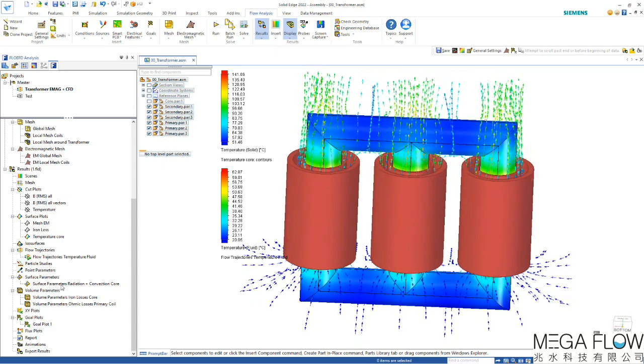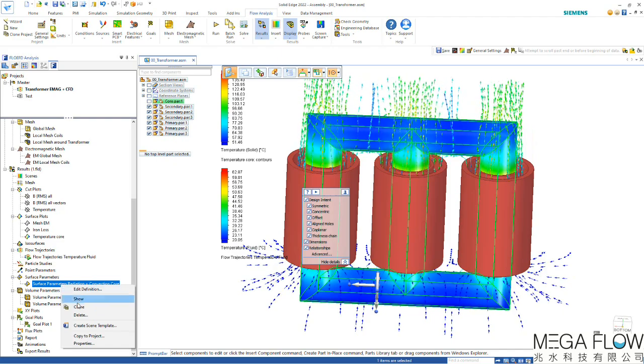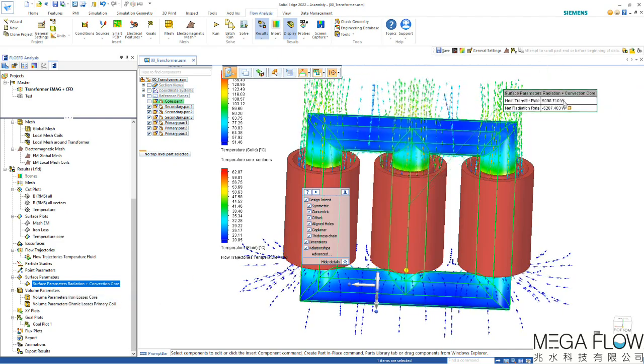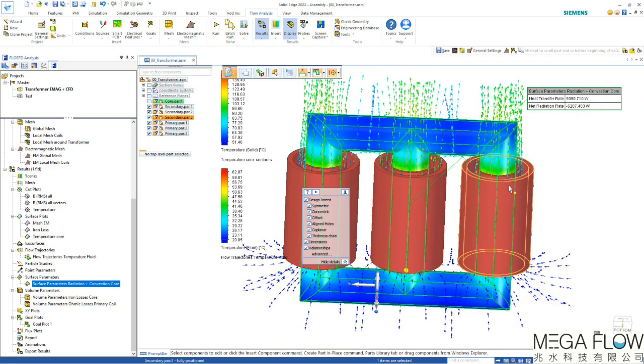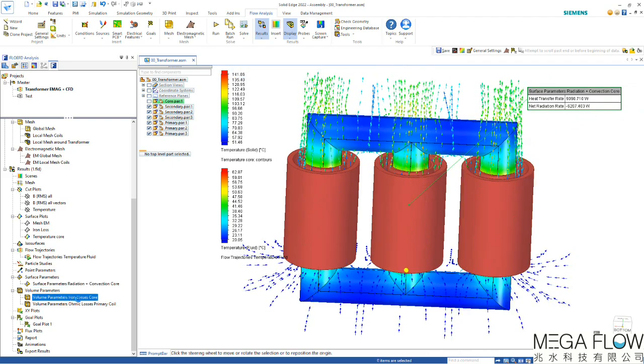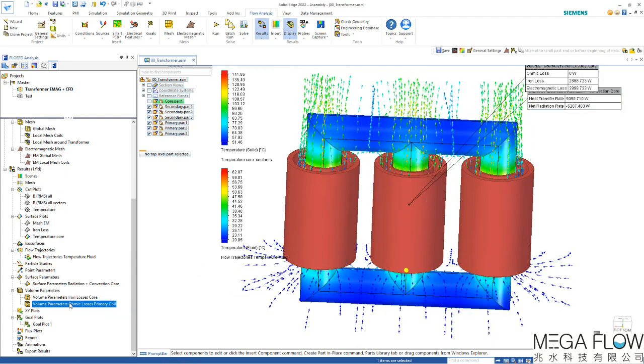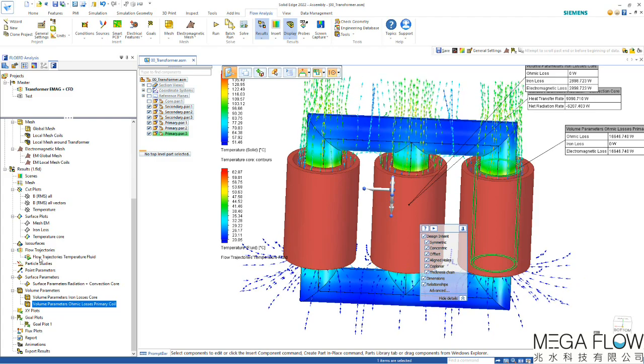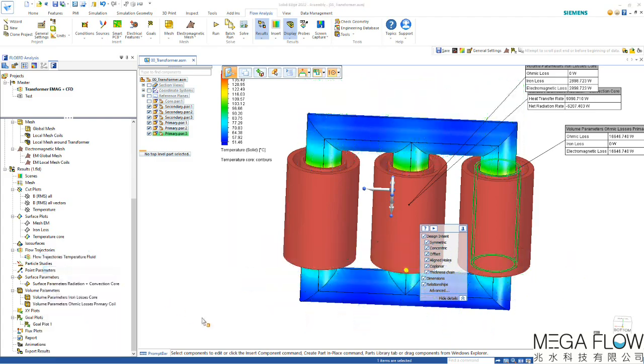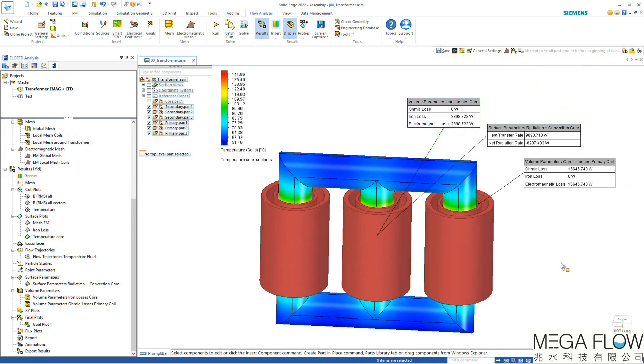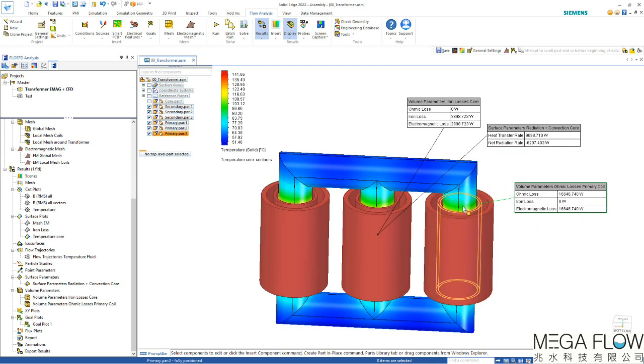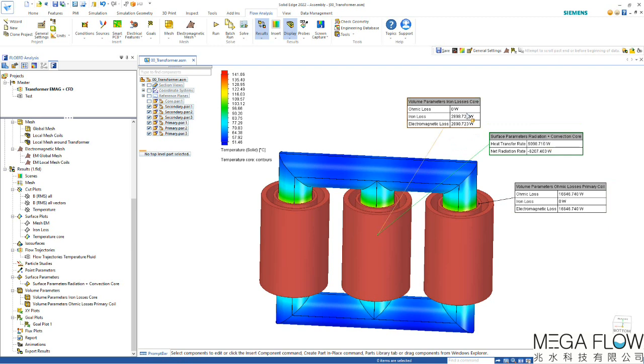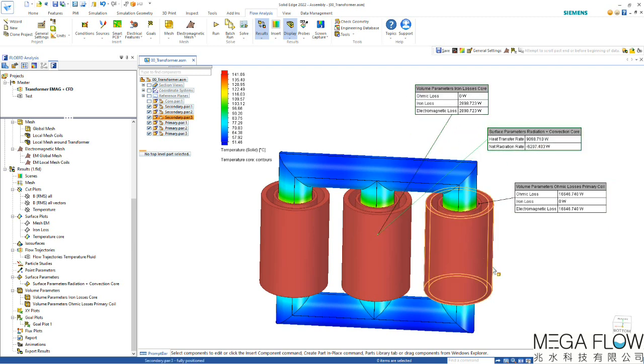If you want to know how much losses there were on the components we can show the surface radiation onto the core, how much the hot copper coils were radiating onto the surface as well as for example the iron losses of the core and the ohmic losses onto the copper coils. Clearly you can see there's a lot of energy being transferred either from the magnetic field onto the core with the iron losses or also through radiation and convection from the copper coils radiating onto the core.